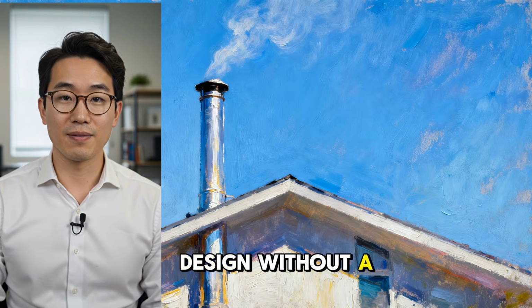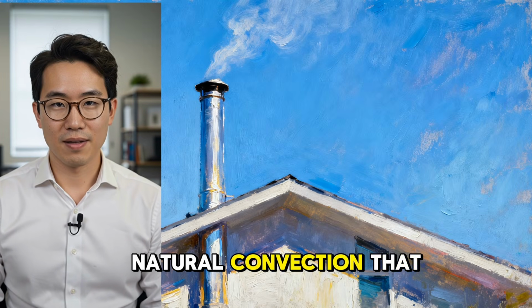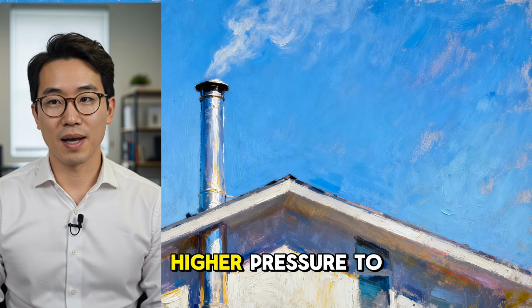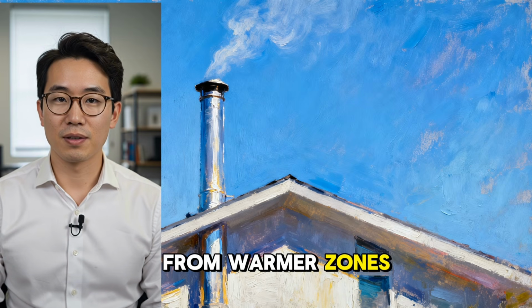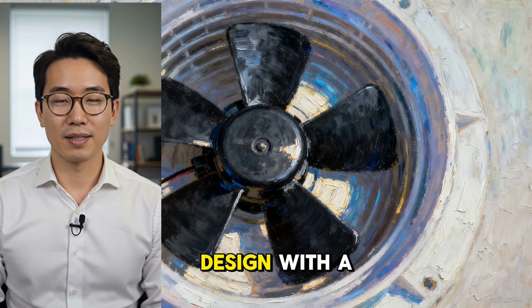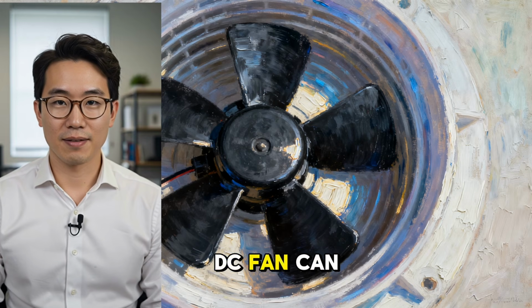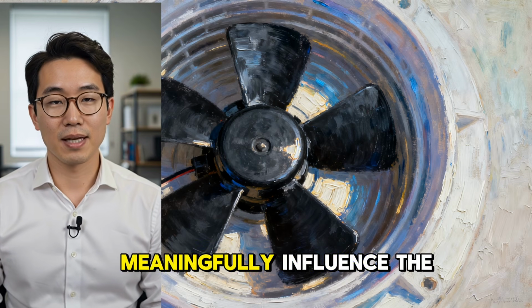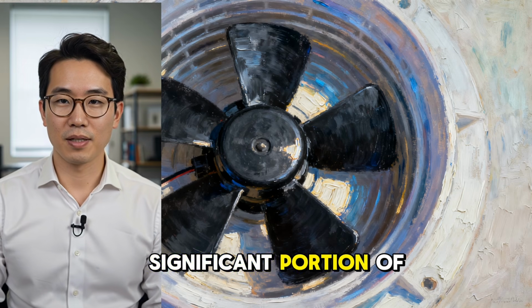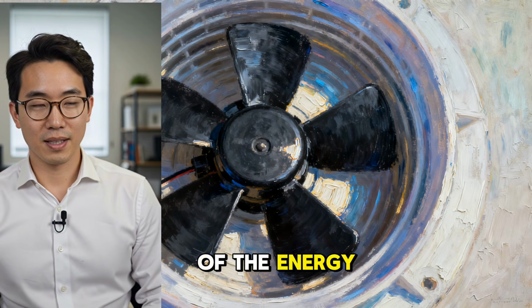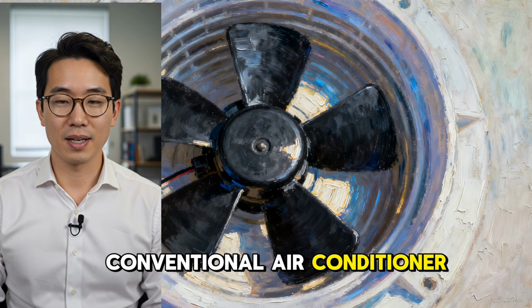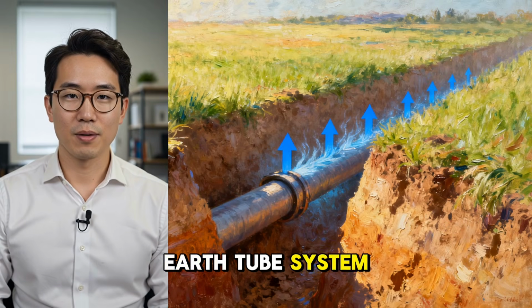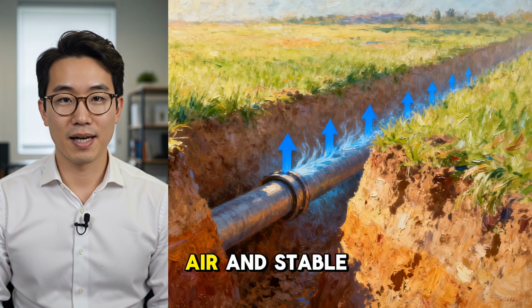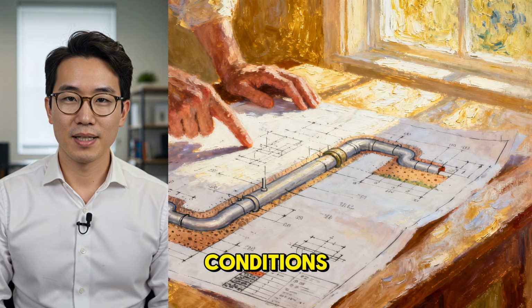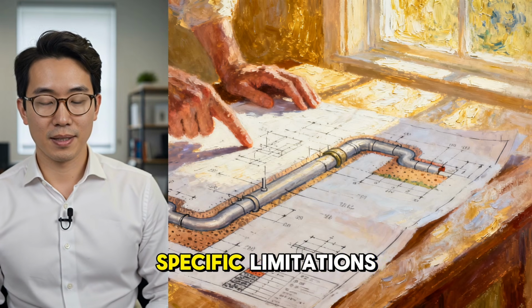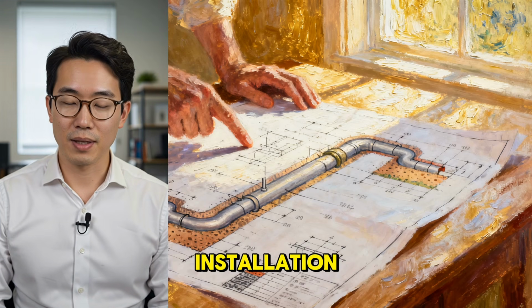In a passive design without a fan, airflow is driven by the same natural convection that drives wind, the movement of air from higher pressure to lower pressure, from warmer zones to cooler ones. In a semi-passive design with a small fan, a 20-watt DC fan can move enough air through the system to meaningfully influence the temperature of a significant portion of a home's interior, at a fraction of the energy cost of even the most efficient conventional air conditioner. Now, because the earth tube system works through direct temperature exchange between moving air and stable soil, it has specific conditions under which it performs best and specific limitations that must be understood before installation.